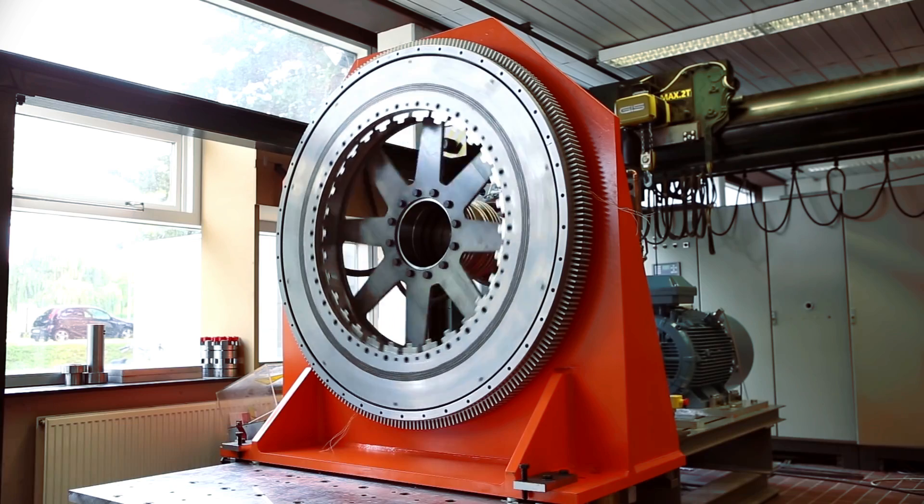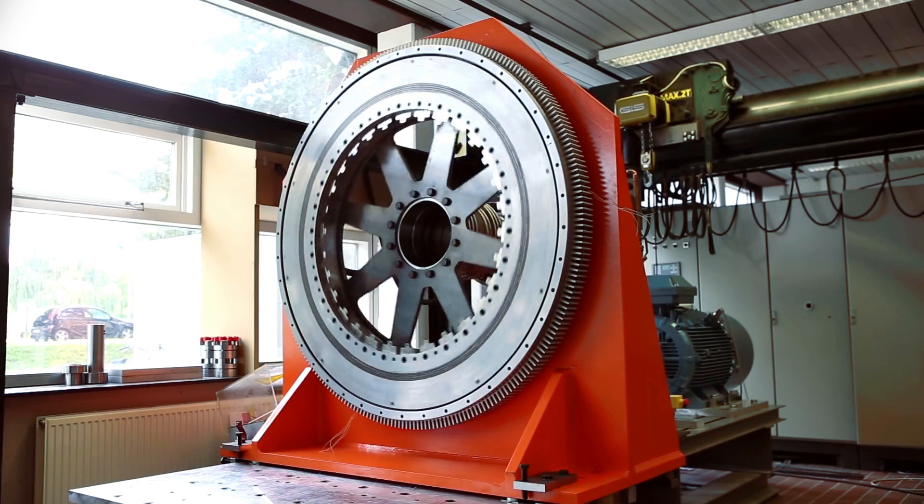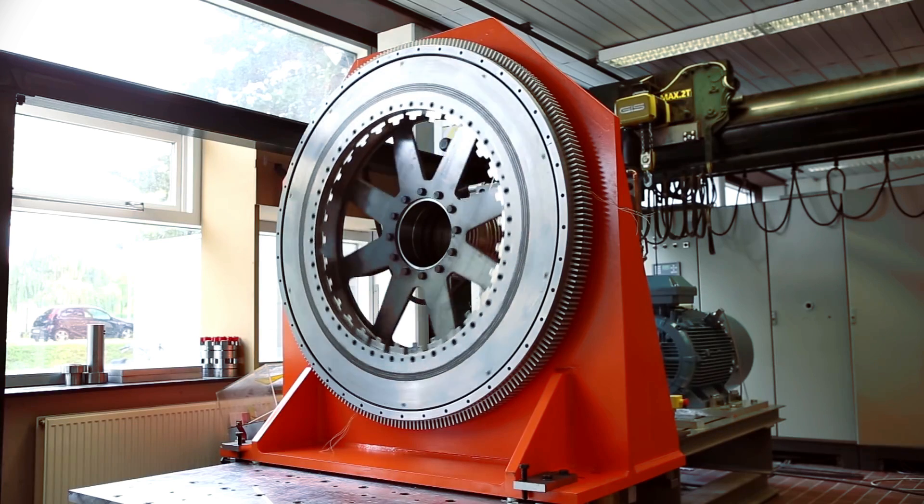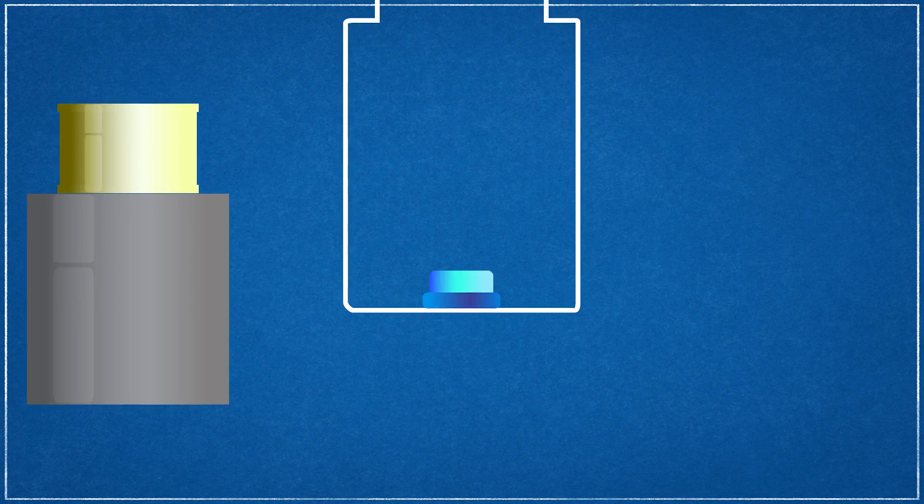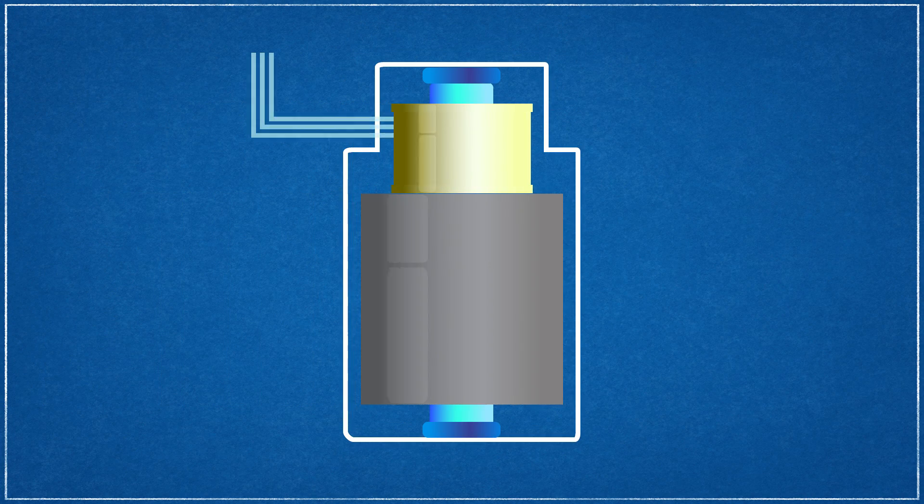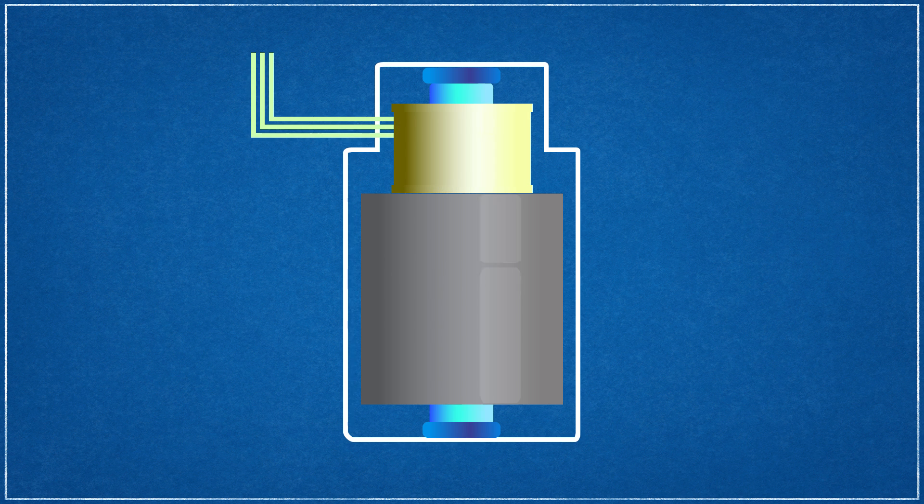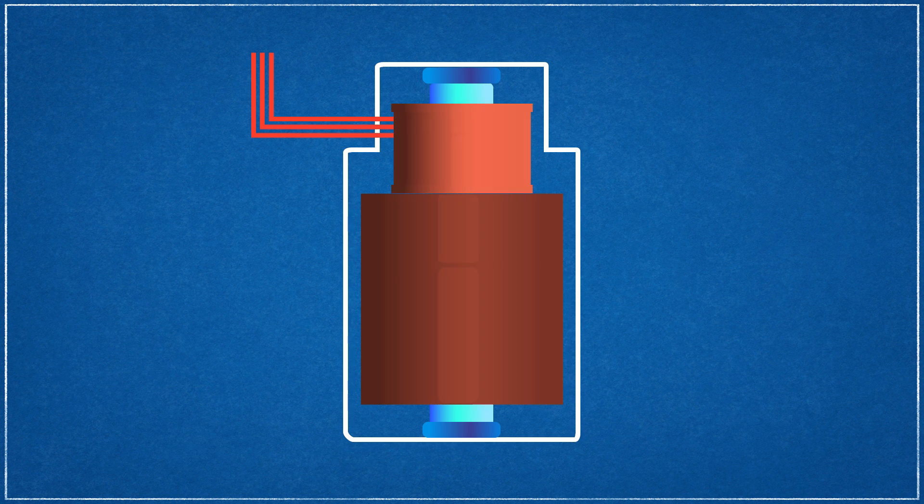The usable rotational speed range of the system is capped by the voltage variation limits of the motor generator system. If the rotor's speed drops below a minimum limit, it will produce too low voltage when discharging the flywheel rotor, while spinning it too quickly during charging can exceed the torque limits of the motor generator. These limitations of the motor generator system itself will always result in a region of inaccessible storage energy capacity within a flywheel energy storage system.